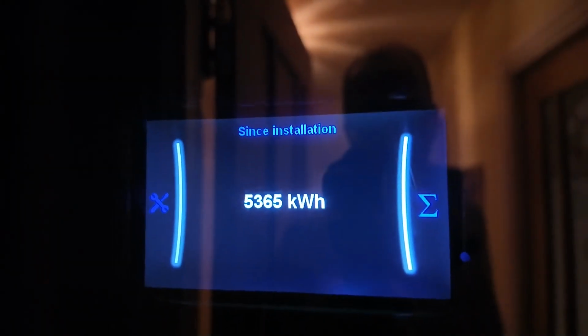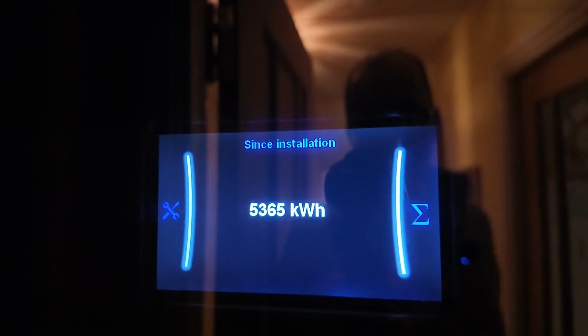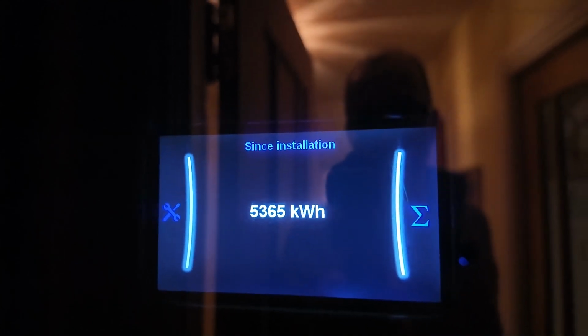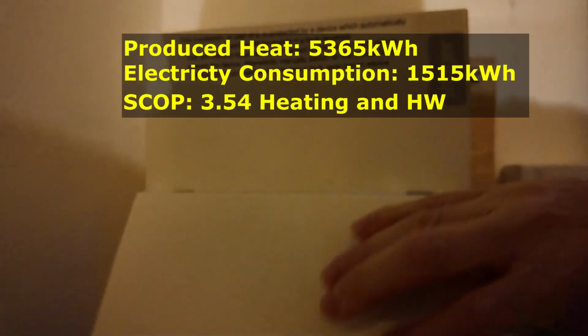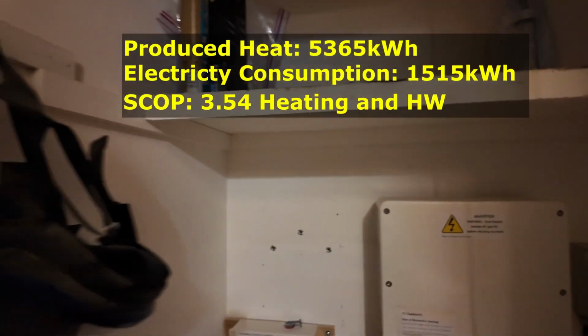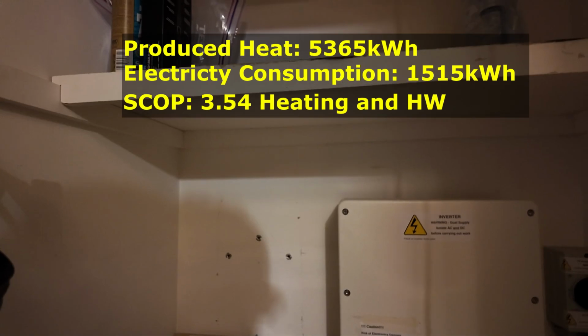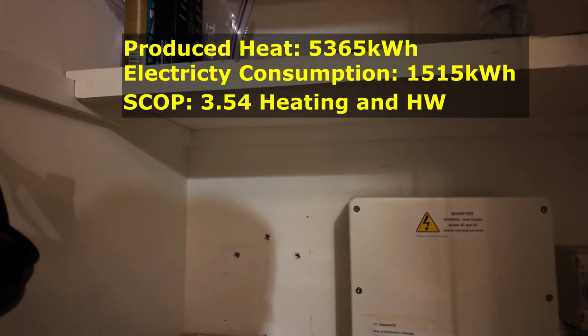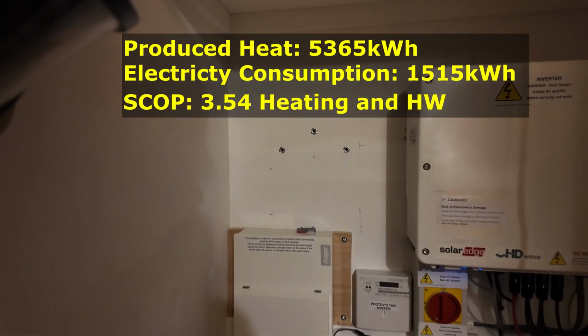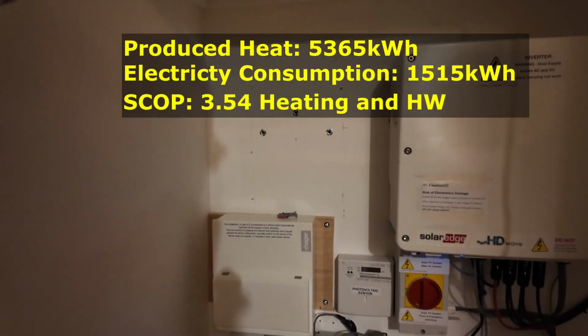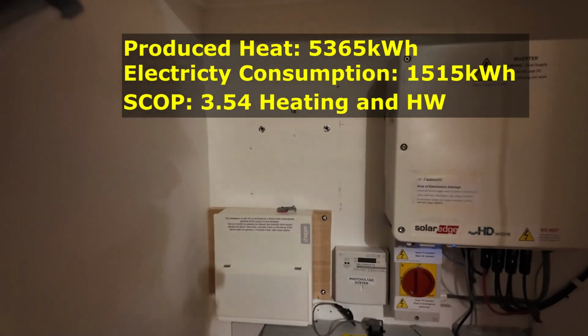So this is the total amount of heat which has been produced, hot water and central heating, 5.3 megawatt hours. And if we have a look at the meter here, 1.5 megawatt hours of input. So that is a seasonal coefficient of performance, which is about 3.5. Not bad for both heating and hot water. Let's go and see how those numbers compare with my analysis tool.